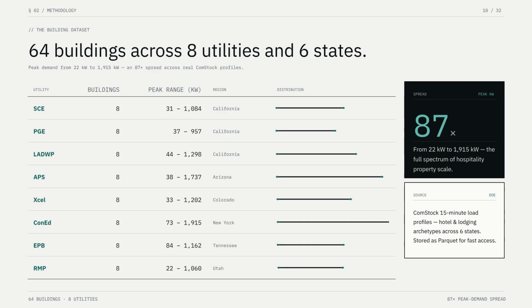The data set, 64 buildings across 8 utilities in 6 states. The peak demand spread is 87 times, from a 22 kilowatt property to a nearly 2 megawatt property. That matters because it means the findings apply across the full spectrum of hospitality buildings, not just one segment.